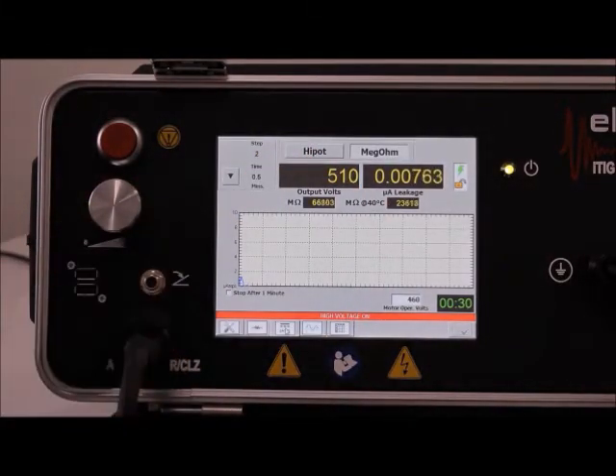The chart near the center here shows the real-time leakage. You also have the option of selecting to do a stop after 1 minute, which means that the tester will automatically shut off the test set after 1 minute has passed. It will automatically calculate the DAR, the dielectric absorption ratio, after a full minute of testing. If you let it run for 10 minutes, it will automatically calculate your PI. So let's see what it looks like for the 1 minute here, and the DAR.